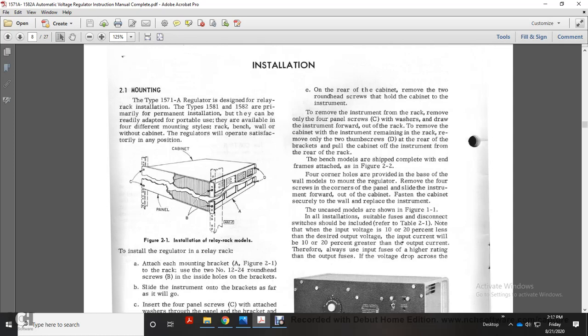On the rear of the cabinet, remove the two round head screws that hold the cabinet to the instrument. To remove the instrument from the rack, remove only the four panel screws with washers, and draw the instrument forward out of the rack. To remove the cabinet with the instrument remaining in the rack, remove only the two thumbscrews D at the rear of the bracket. Pull the cabinet off the instrument toward the rear of the rack.